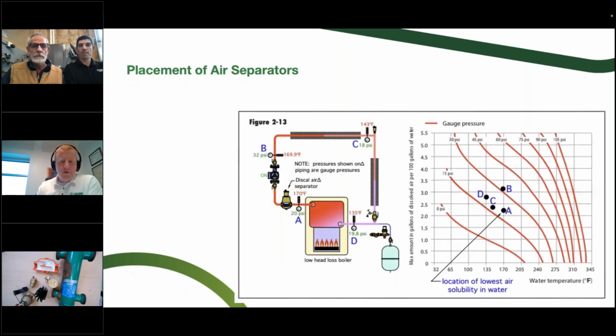For sure. We also see some of those actually where they get installed with strainers too, which can really slow down flow if they get plugged up and things like that. And personally, especially on a heating system, I always like to see the air removal and the dirt removal in 2 separate spots, because that's where it's ideally placed, which we'll get to later, I'm sure. But definitely not good to have that thing all plugged up full of debris.